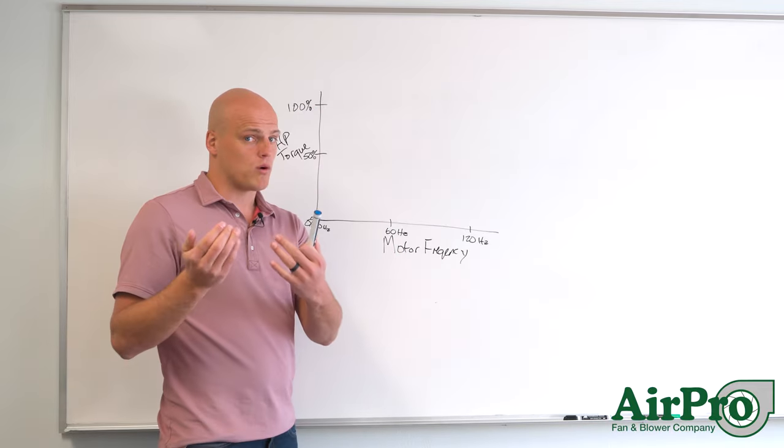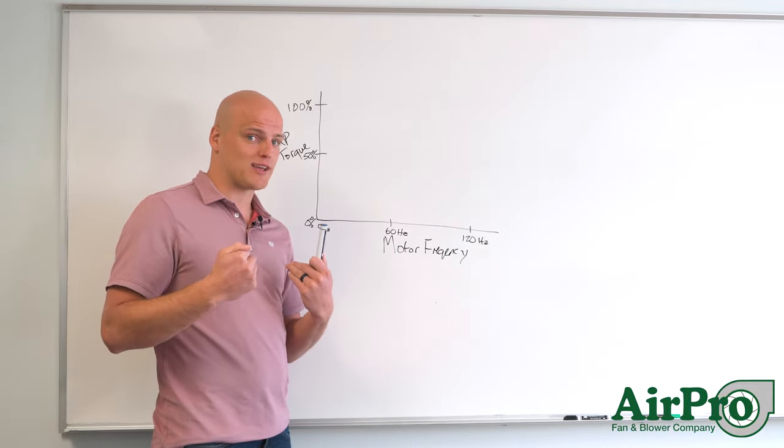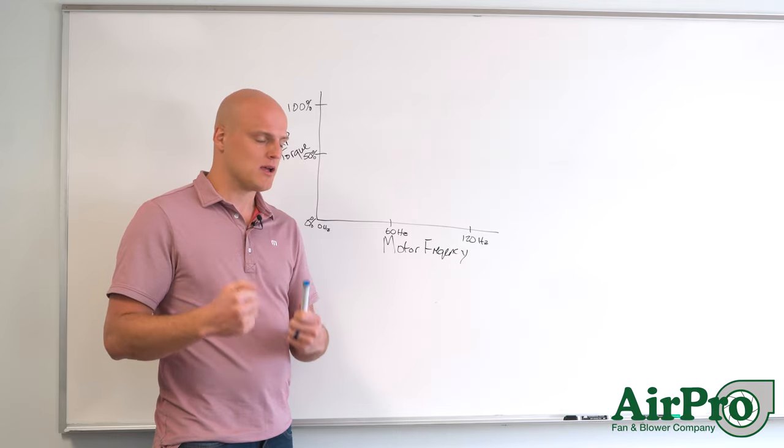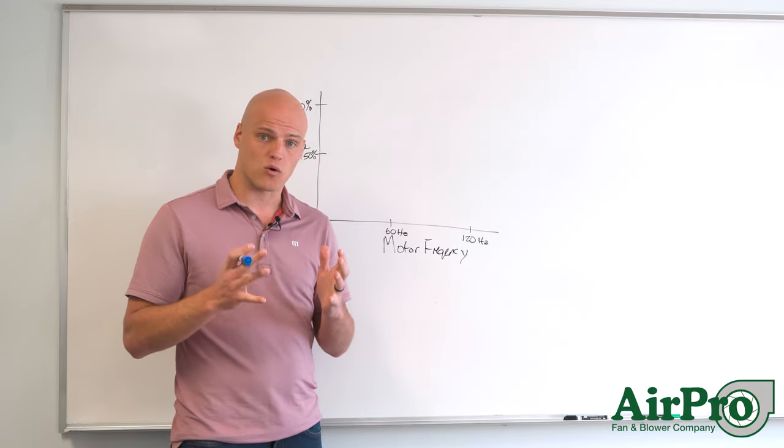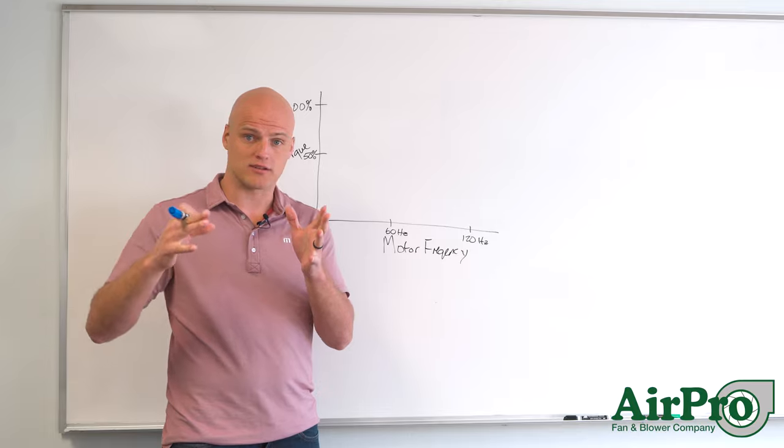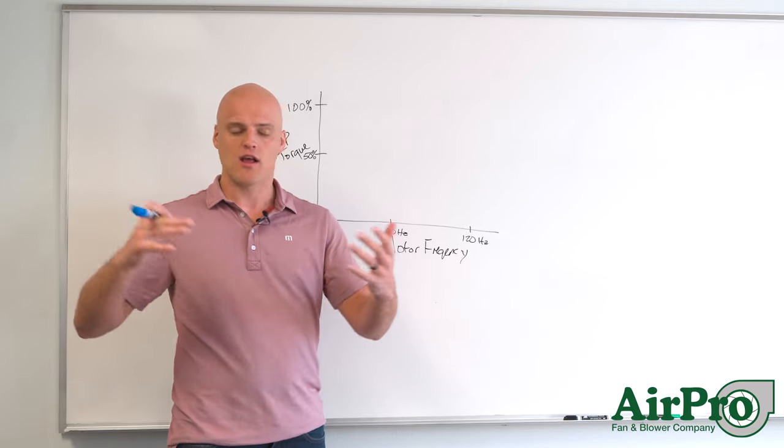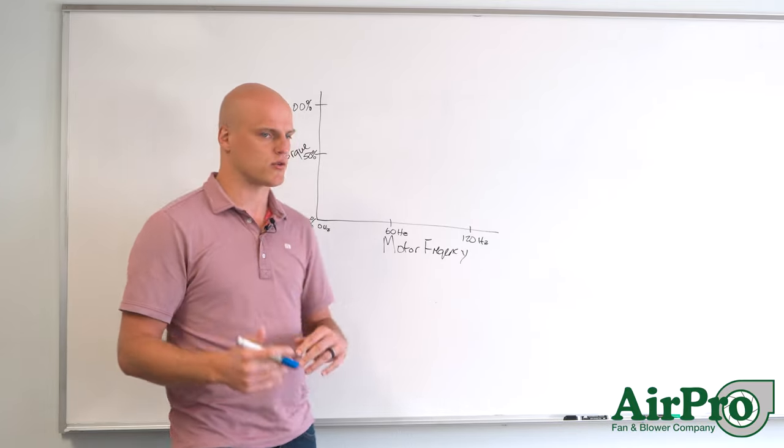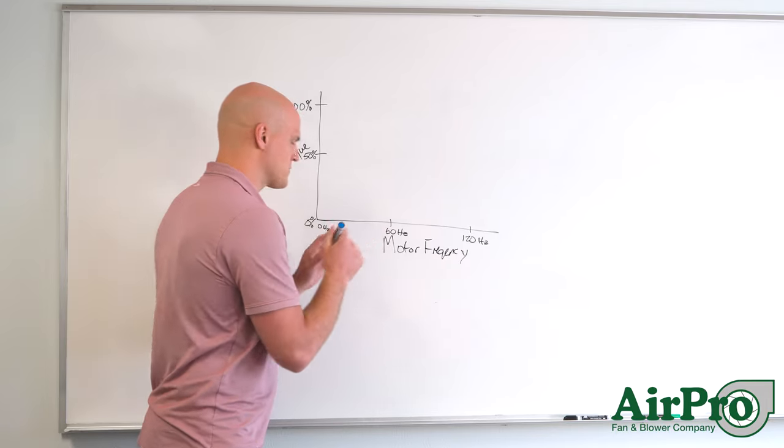So what we care about more than torque is horsepower availability because you always need a certain horsepower to drive this fan to be moving the type of air through the type of pressure that you're trying to move it through. So we're going to look at horsepower first.